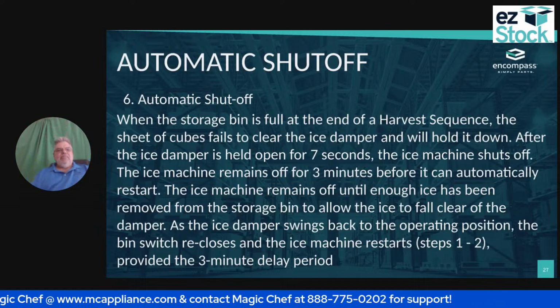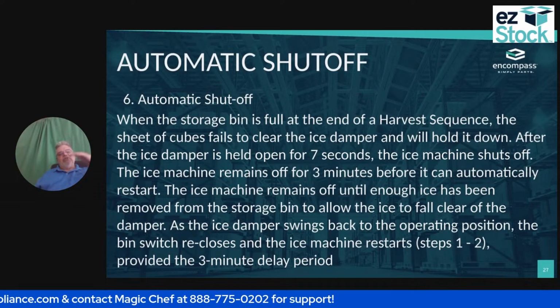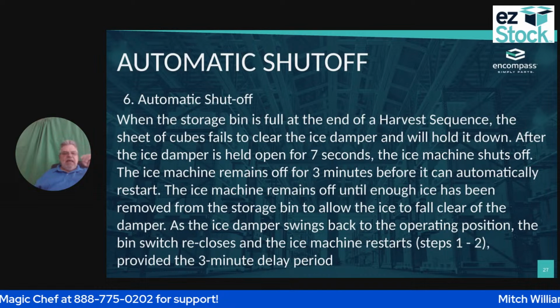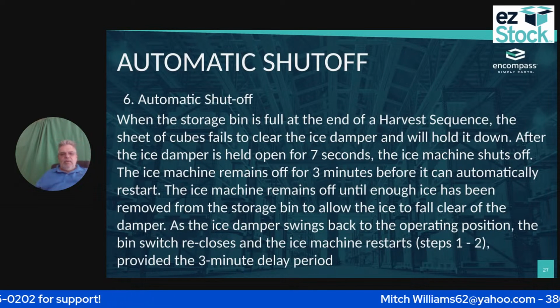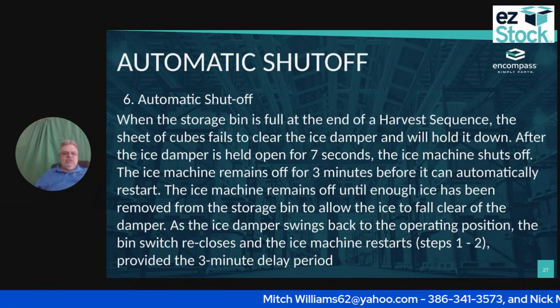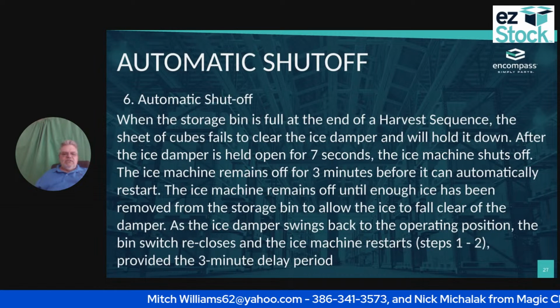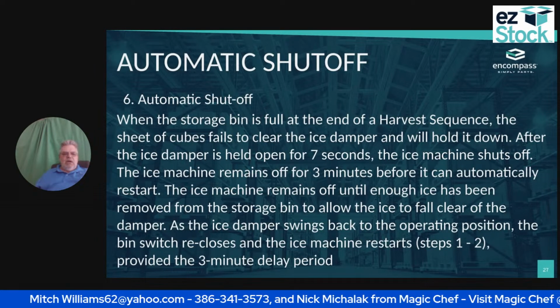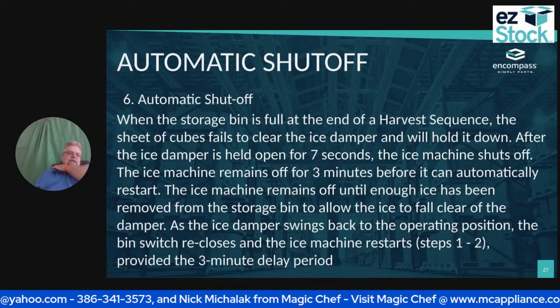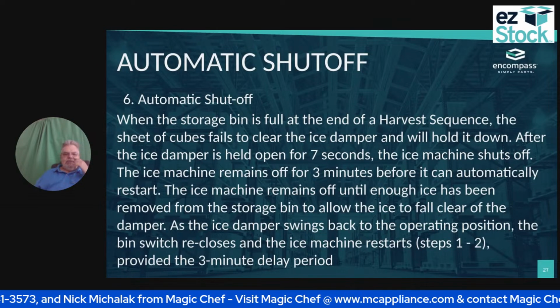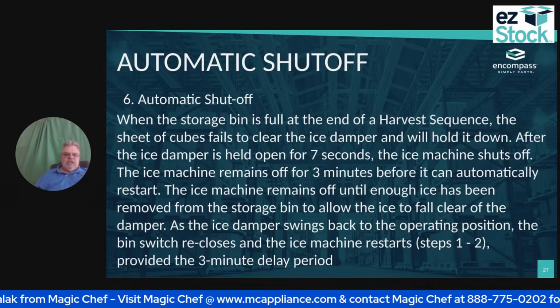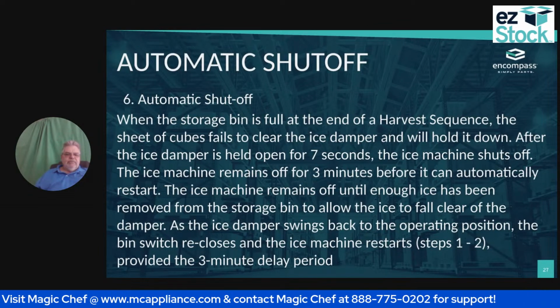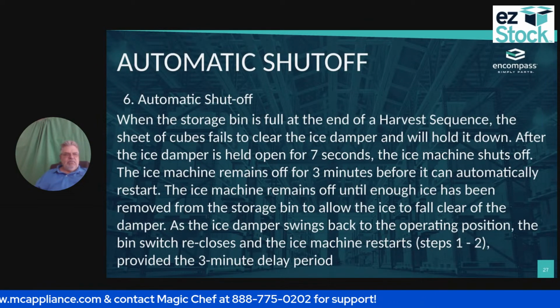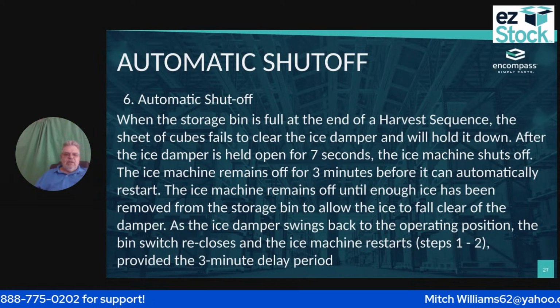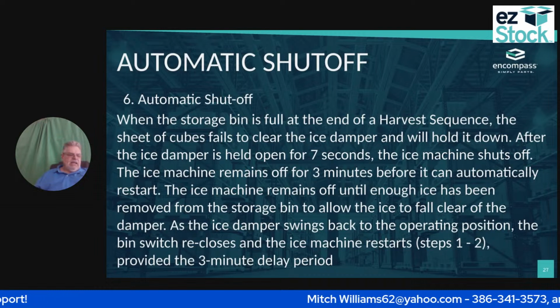Okay, what happens next? As my ice starts to build, I have an automatic shutoff, just like I do in a regular refrigerator. When the ice storage bin is full at the end of the harvest cycle, the sheets of ice fail to clear the ice damper, and it will hold it open. After the ice damper is held open for 7 seconds, the ice machine will shut off, just like it does in a regular ice maker in a refrigerator. The ice machine remains off for 3 minutes before it can automatically restart.